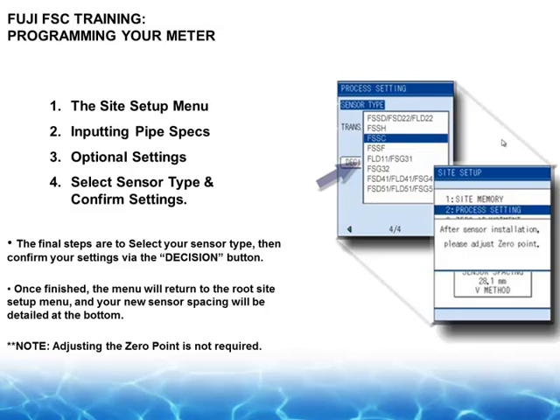Now, one screen pops up that still gives me a hissy fit. It says, after sensor installation, please adjust 0 point. And if you learned anything from us, don't touch the 0. No. Don't touch the 0. The 0 on the meter is just fine. If you have adjusted the 0, give us a call. We'll show you how to reset it. It's not a big deal. But you cannot get a 0 reference.